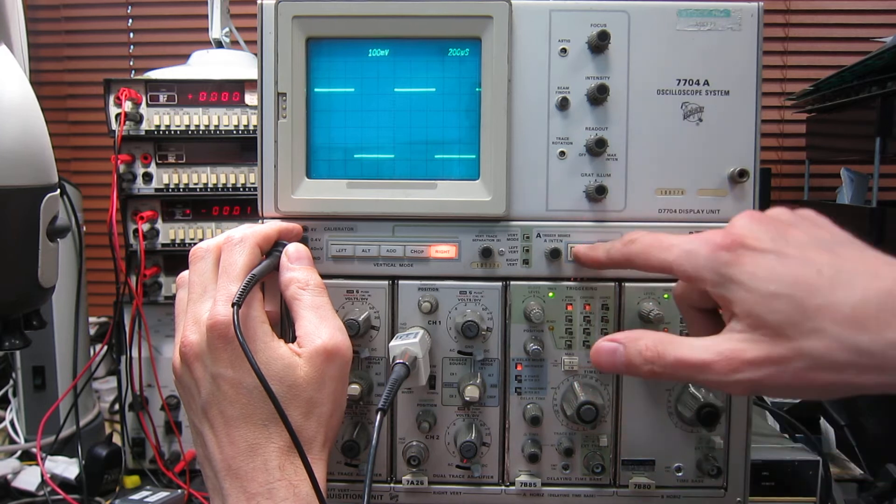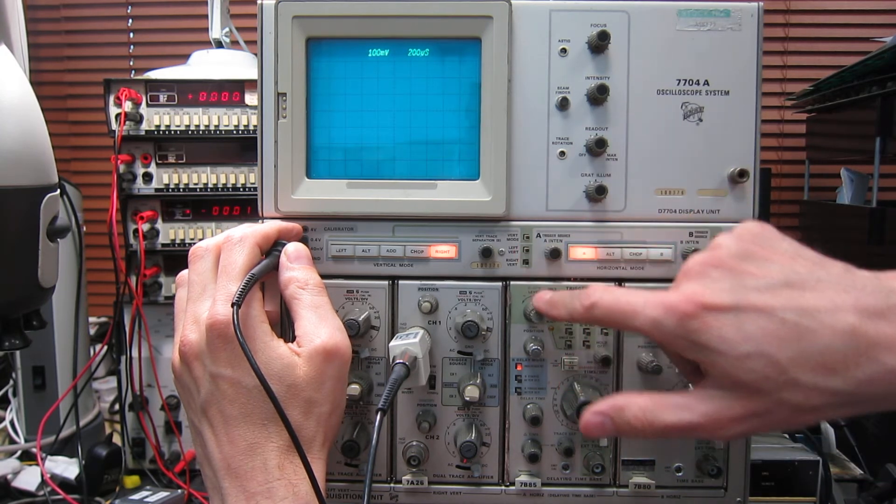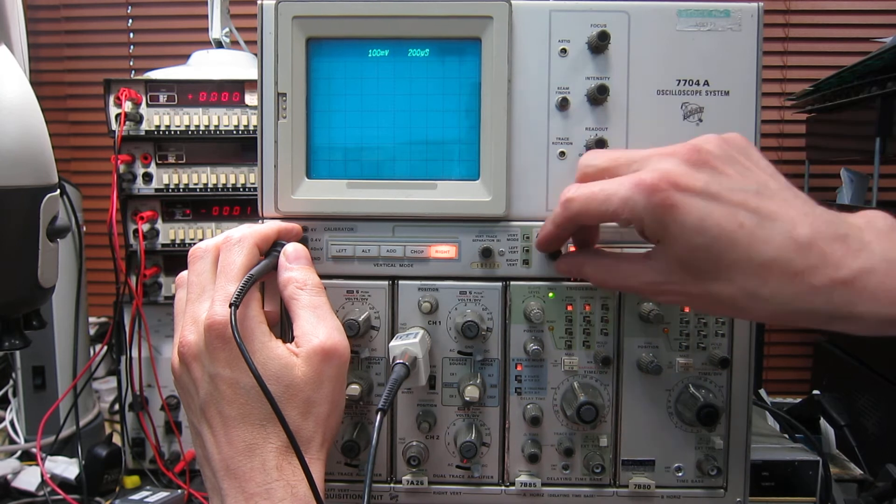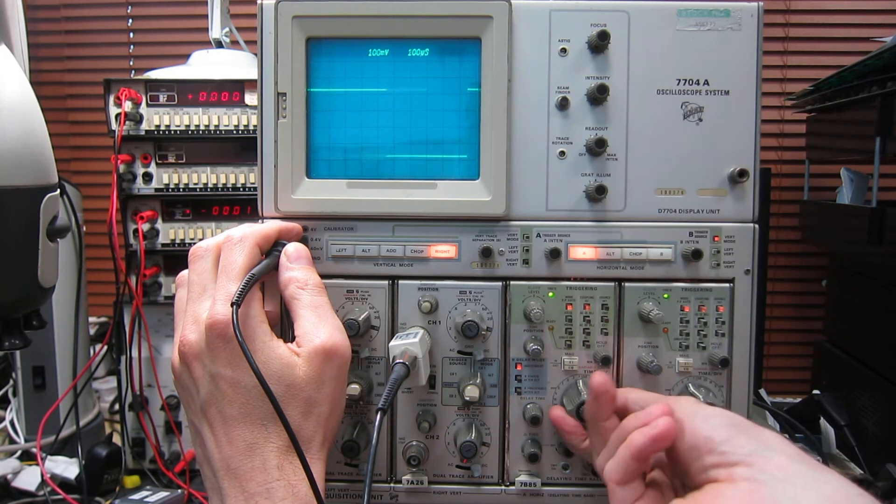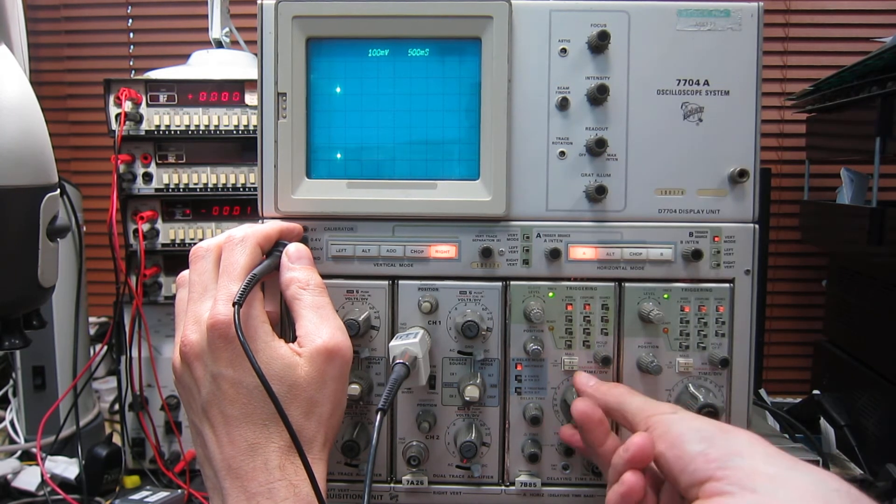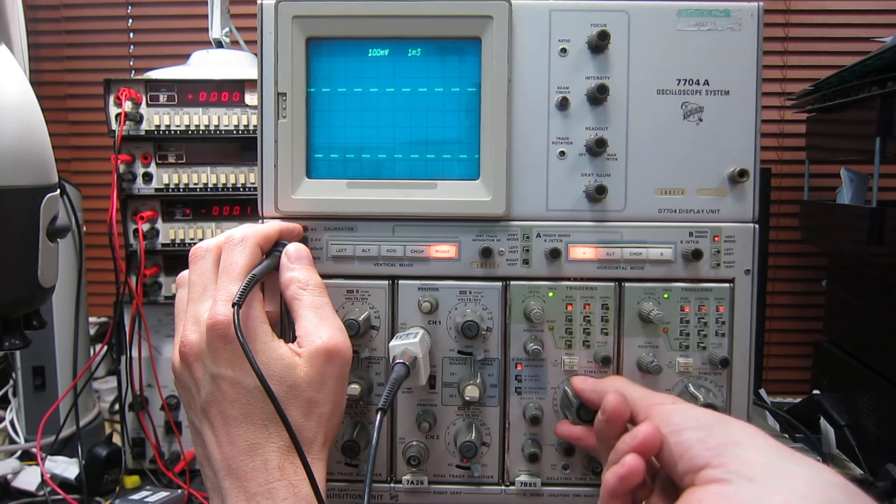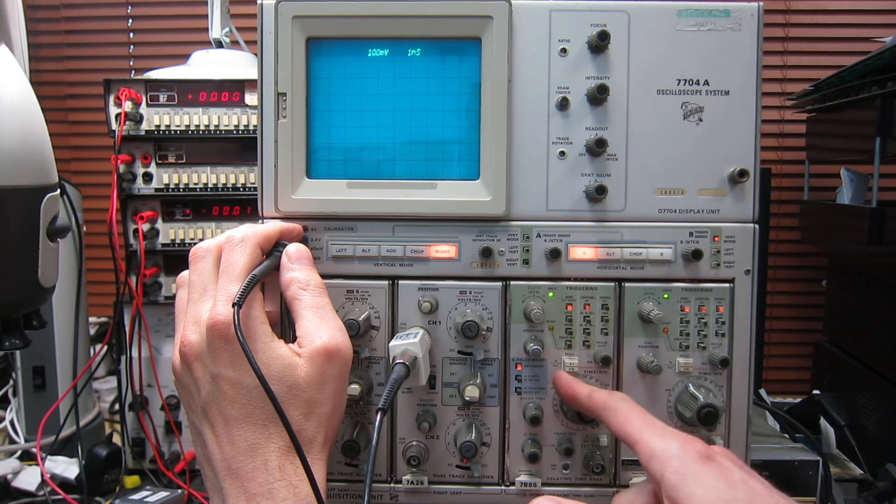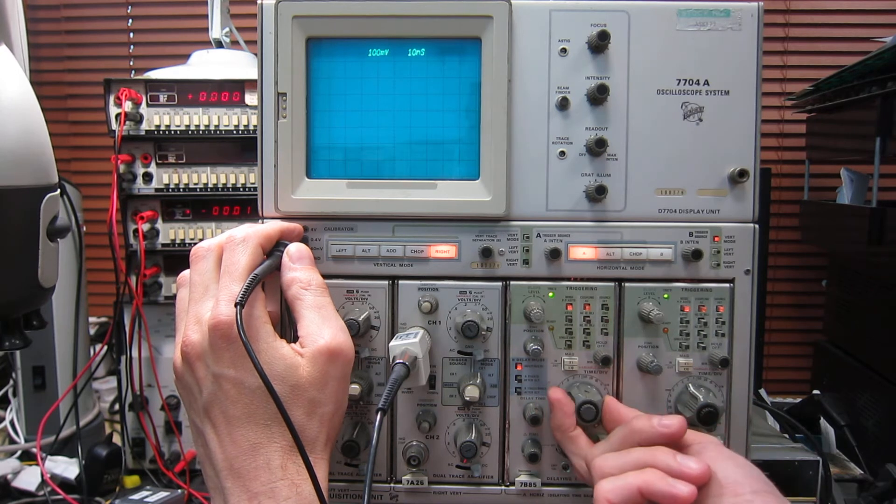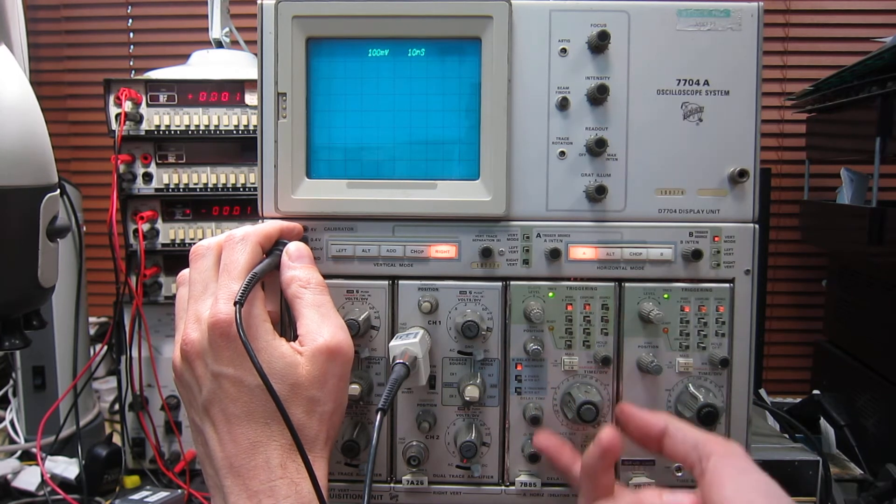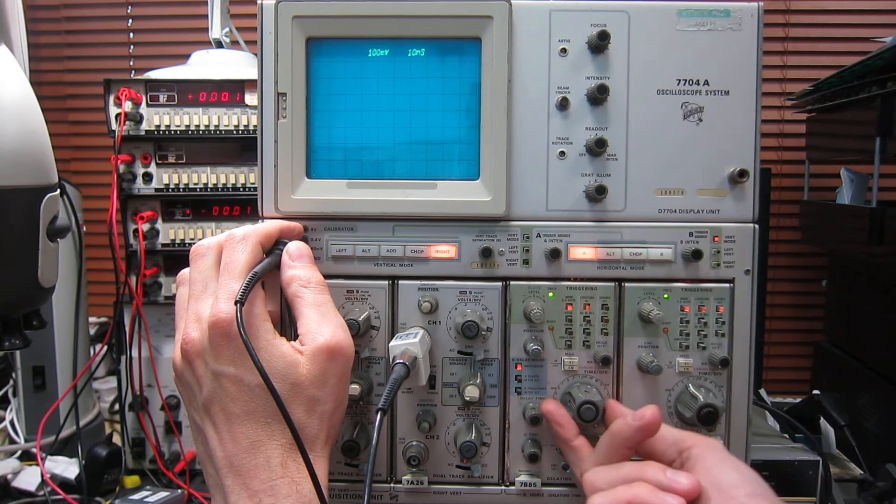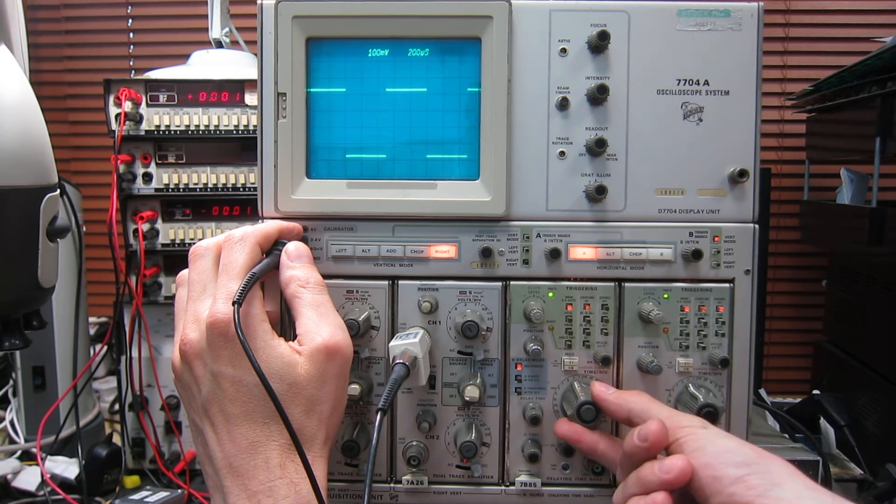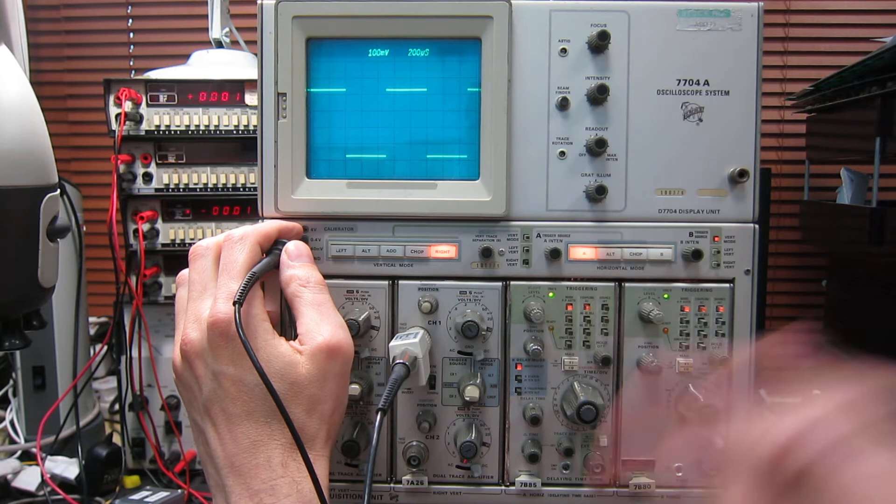We'll do the same on time base A. There we go. Again, five seconds per centimetre all the way up to, when we put the magnifier on, 10 nanoseconds per centimetre. You can't see it at the fast rates because this is a one kilohertz waveform, so it's triggering infrequently. So time bases are working.